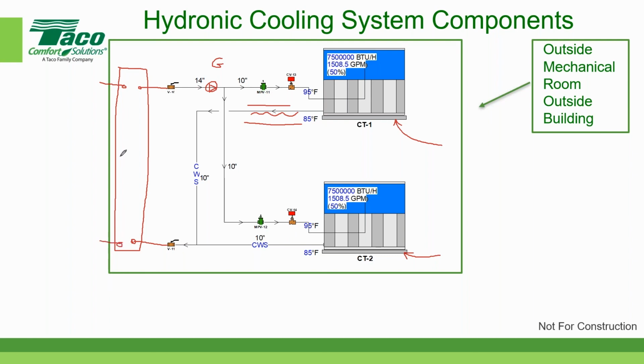And typically the plate and frame, this would be a representative of plate and frame, is physically inside the building. So then I can have glycol outside if it's a closed loop cooling tower. Remember, you can't have glycol in an open loop cooling tower because you can't evaporate glycol for cooling purposes. Well, even if you could, you wouldn't, because it would cost a fortune to evaporate glycol. And then on the inside of the building, it's all water over here. So that minimizes the amount of glycol that's used. So hopefully that gives some guidance.